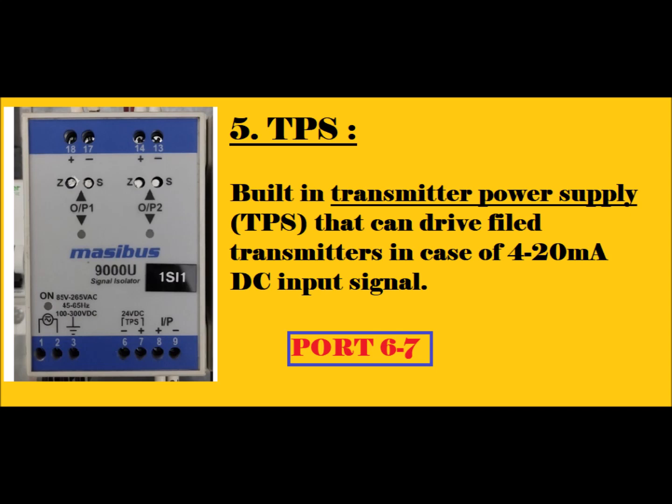The next point is TPS — Transmitter Power Supply. Just imagine that equipment is installed in the field and it requires 24V DC. With the help of the Signal Isolator, this supply is provided through ports 6 and 7 — positive and negative — because it is a DC power supply.